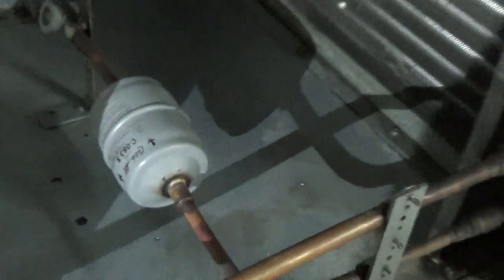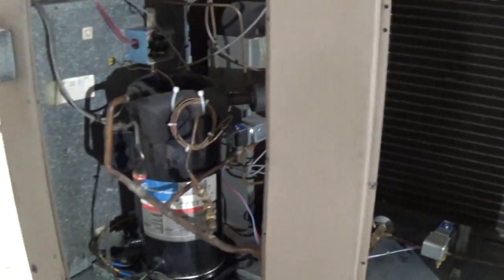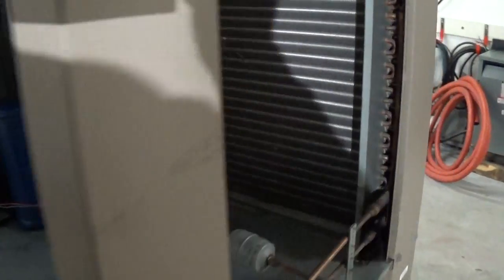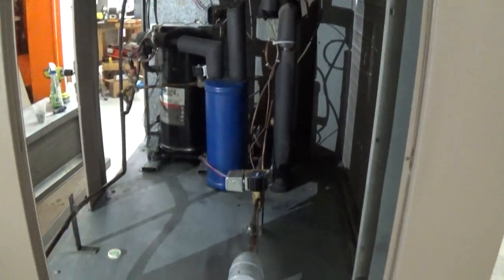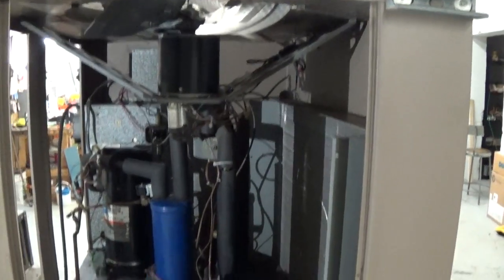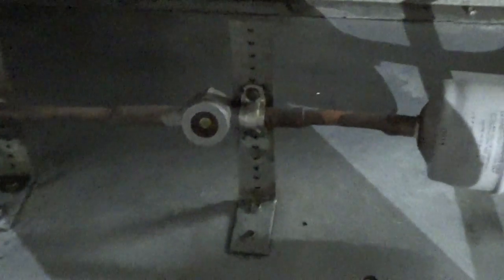Here we have our dryer and our refrigerant circuit. Again, it's key that in the top section here with this condenser design, you have to have all these top covers on to give appropriate airflow through the condenser when you are running. Here we have our sight glass, nice and green, what you want to see. We'll put the cover back on.